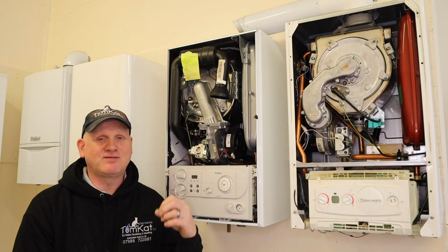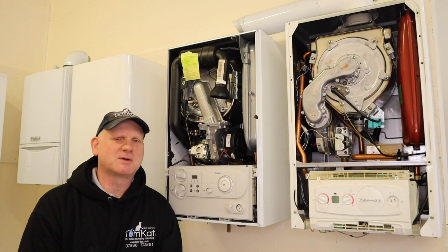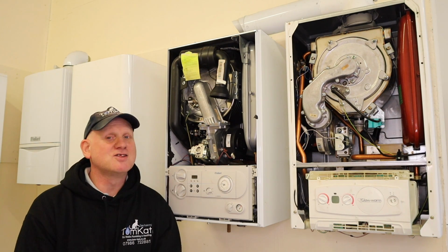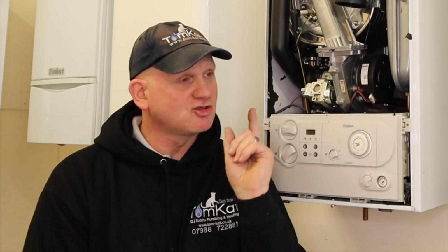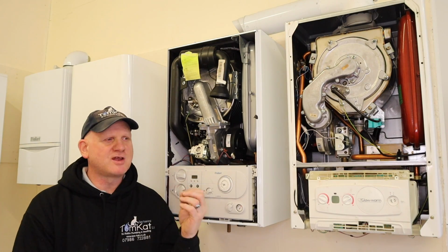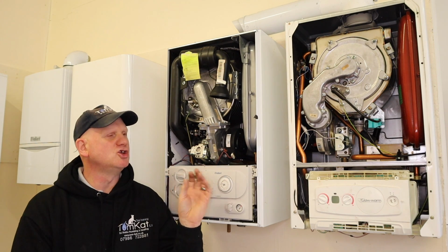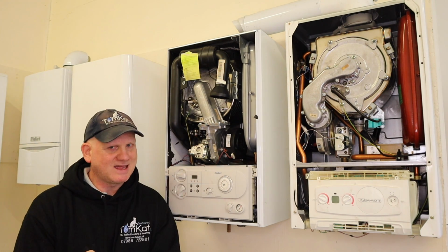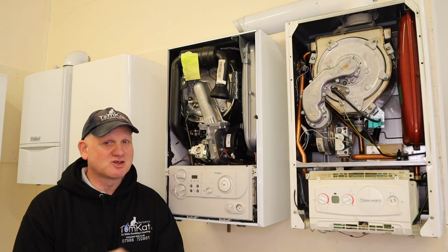And it must also be understood that the performance of the stainless steel is dependent on the amount of chromium that is actually in the metal. So basically, in a nutshell, that means if the stainless steel isn't of a very high grade, about 316 stainless steel they say, then it's not very good for a heat exchanger. There are many different types of stainless steel used in heat exchangers, and some manufacturers weld their stainless steel and some don't, to make it less likely to block up with magnetite. So like I say, 316 stainless steel is the main stainless steel used for heat exchangers because of its weldability and its resistance to corrosion.